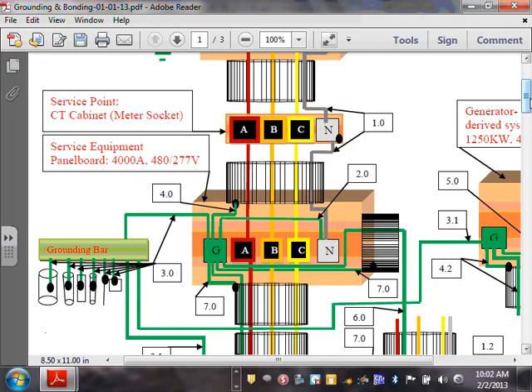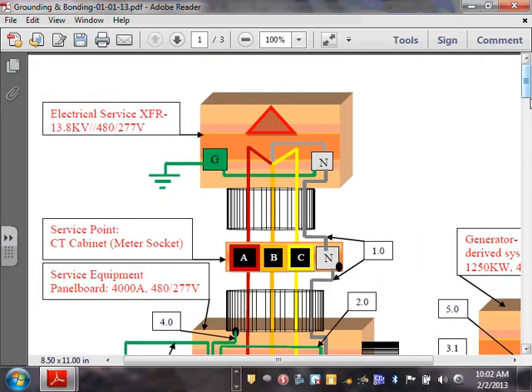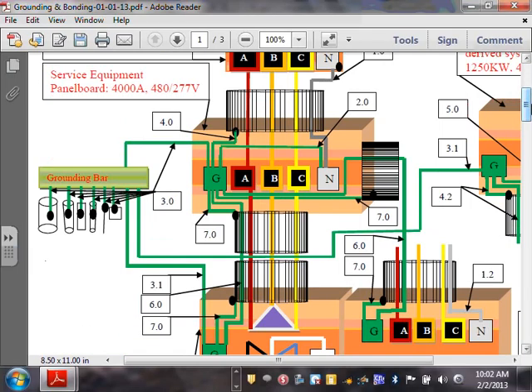Anybody have used a ground plate, cover plate to supplement your grounding? Ground plate? Oops, where did it go? So these are all the grounding electrode system, and I forgot what that was. What else did we forget about the approved grounding electrode system? The Ufer ground? Ufer ground, yeah. Concrete encased electrodes. So these are, or any other object in direct contact, like a big tank, not a gas tank, a big tank buried underground for water or something, that qualify as a grounding electrode system.